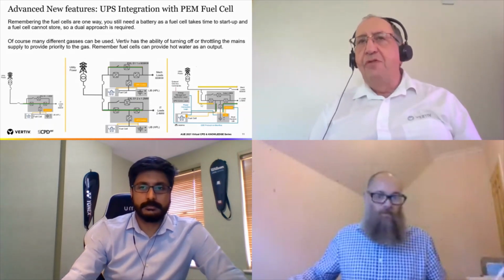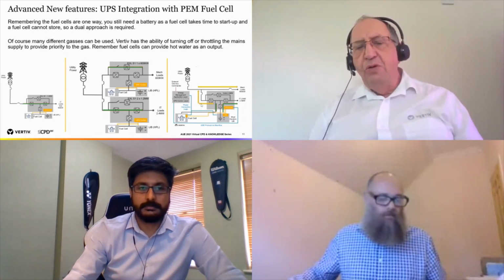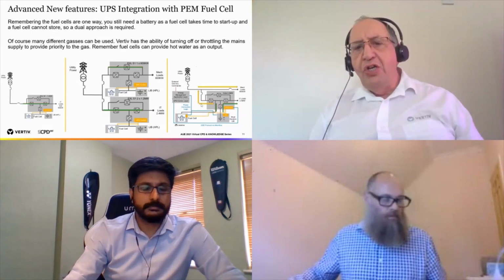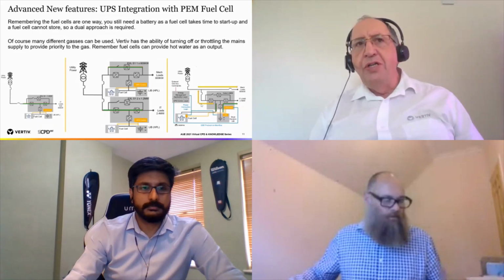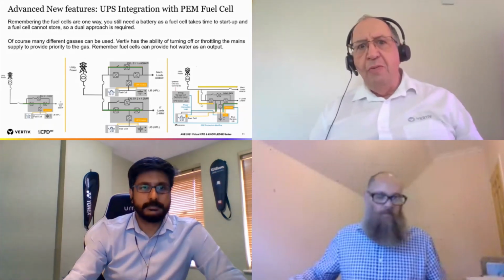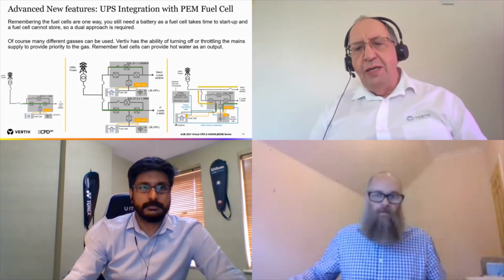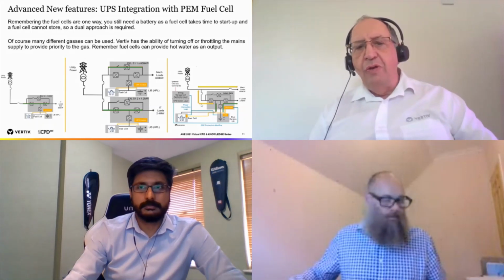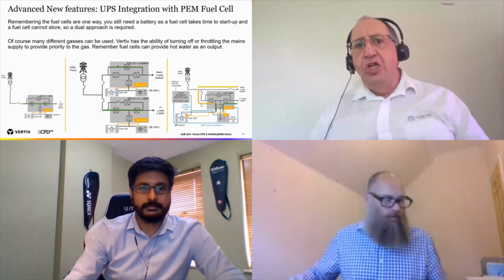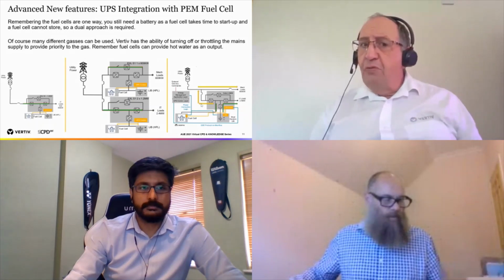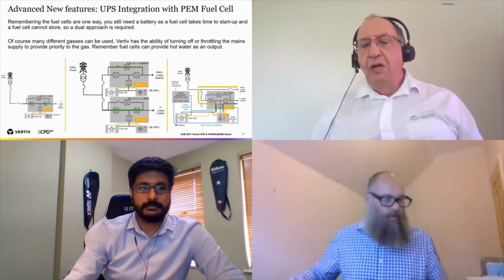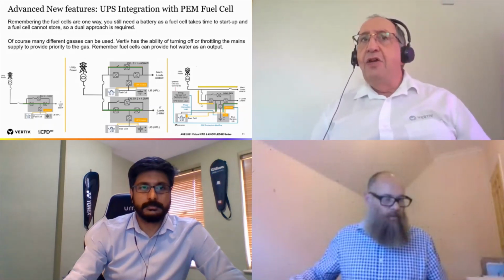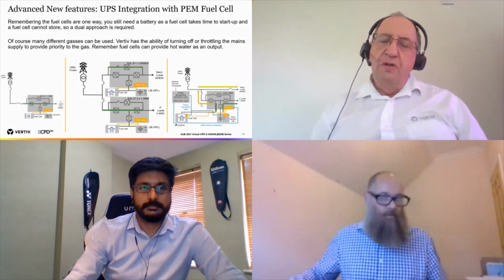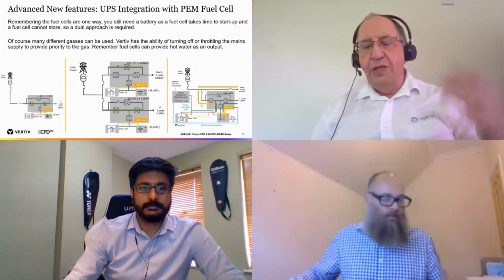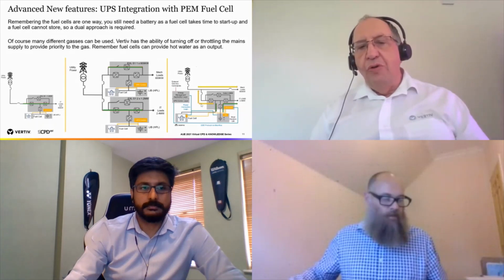One of the things that we have to remember is that the fuel cell is unidirectional, not bidirectional as per the lithium ion battery. So it's important that while that goes on, the lithium ion battery is recharged, maybe from the fuel cell if there's no mains available, so that it can actually take the UPS function should the fuel cell fall over because the gas runs out or there's some other problem with the fuel supply to the fuel cell.